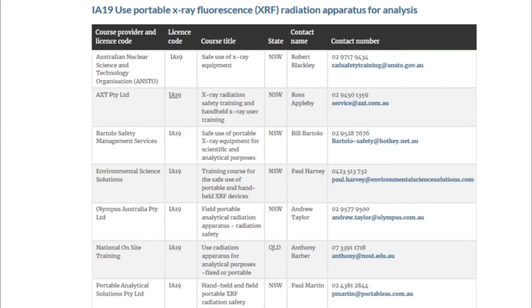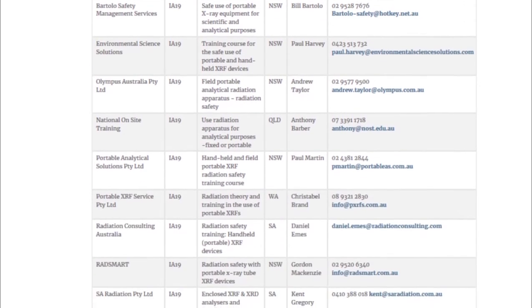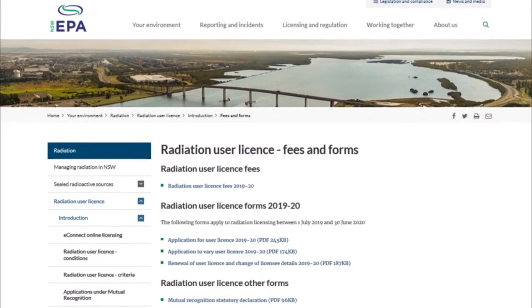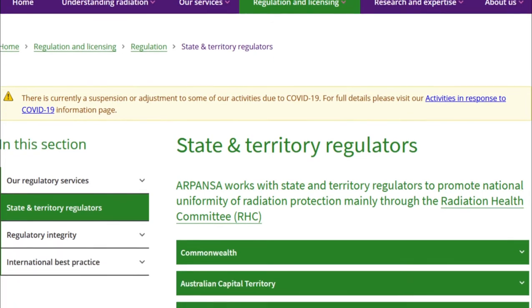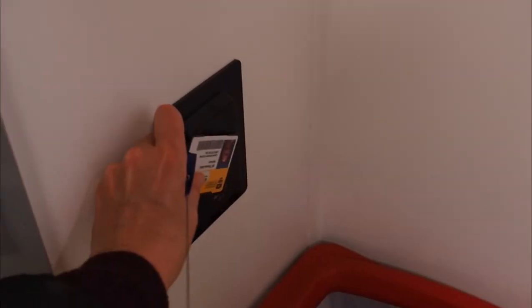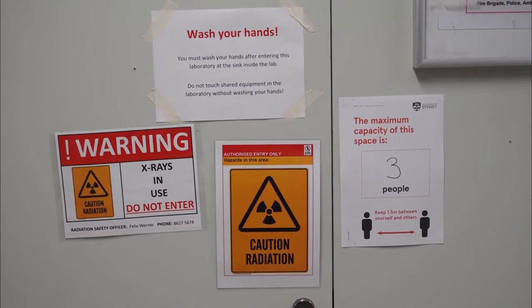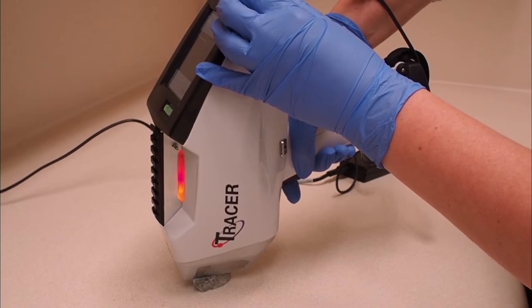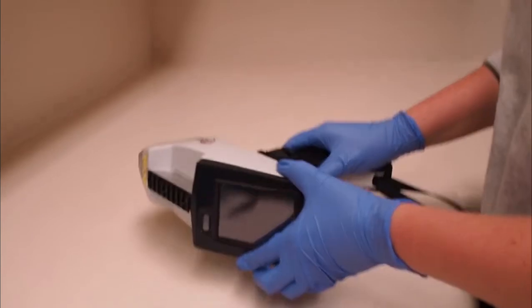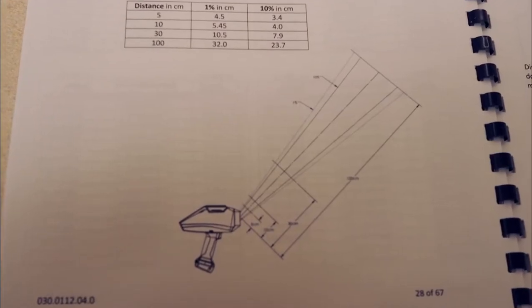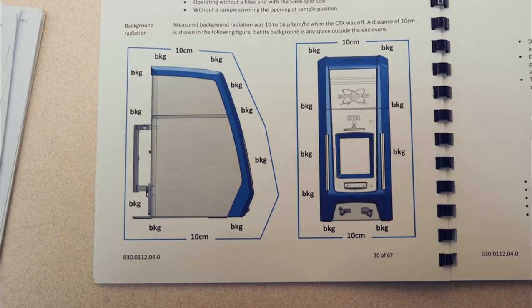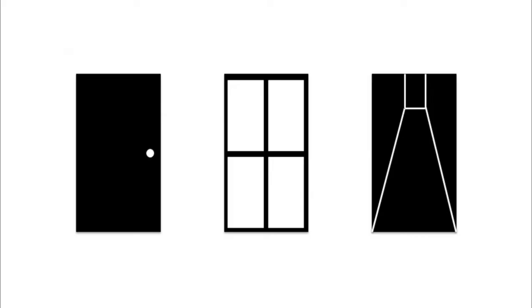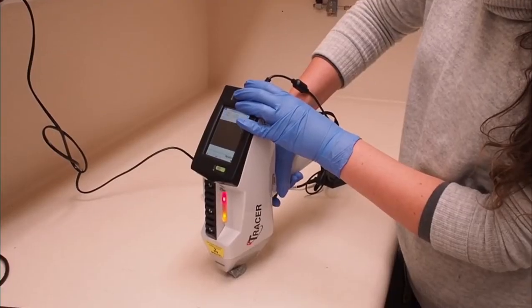As a result, we ask that IA-19 training is undertaken by an EPA recognised course provider, and that subsequently an EPA licence is obtained prior to accessing the tracer. Users who intend to operate the tracer in other states or overseas should contact staff so that we can make the appropriate arrangements. Each state in Australia does have its own ionising radiation safety requirements. Access to the lab is restricted with warning signs in place outside all entry doors, and the tracer also has warning lights to indicate active emission of radiation. Radiation exposure must be monitored with a portable dosimeter. When using the tracer, you must keep in mind where the radiation is being directed. For handheld operation, keep your hands behind the trigger and always point the instrument away from yourself and others, and always away from doorways, windows or thoroughfares. At all times, ensure that other people in the room stand behind you and are not in the path of x-rays.